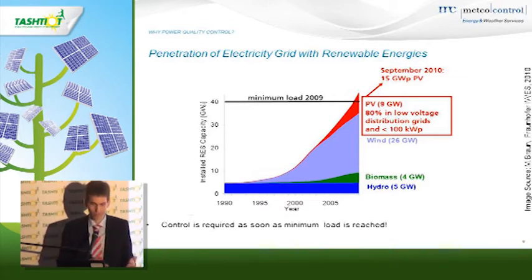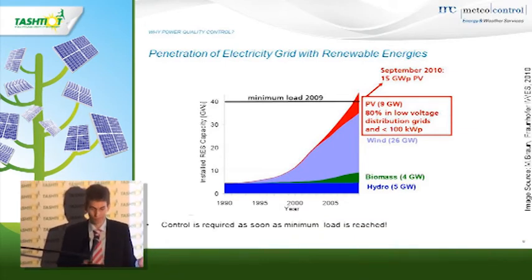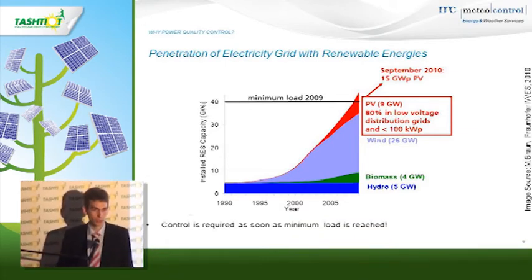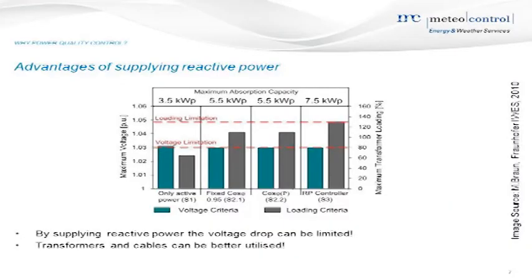So in the bad case that you have a lot of production, a lot of wind, a lot of sun, but a very low demand, like on a holiday, you could have more generation than demand, and therefore you need definitely to control the renewable energies. So this is more for active power control. The other big point is the reactive power control.